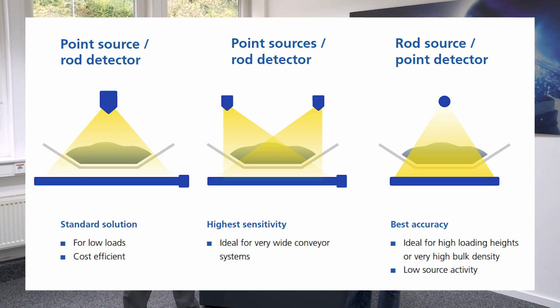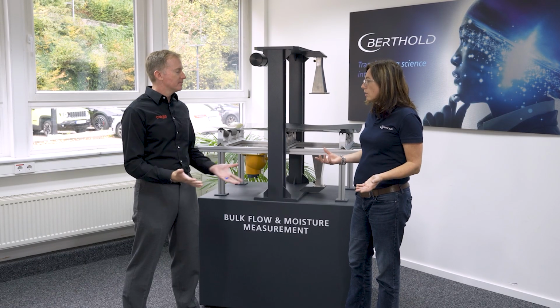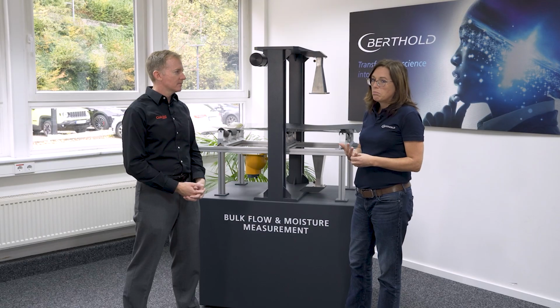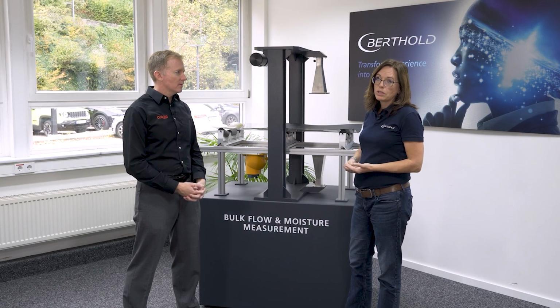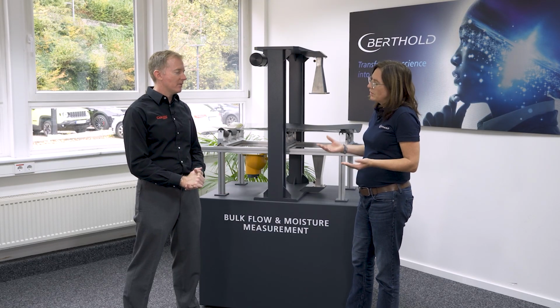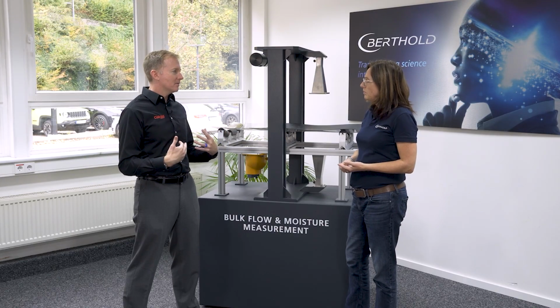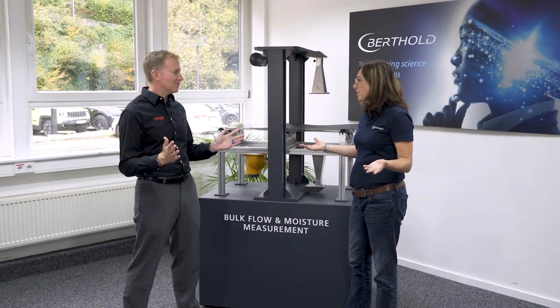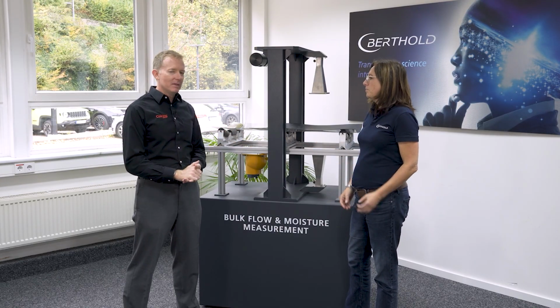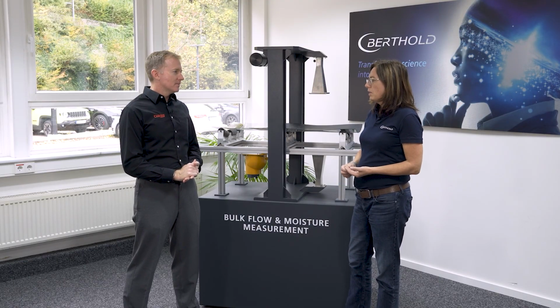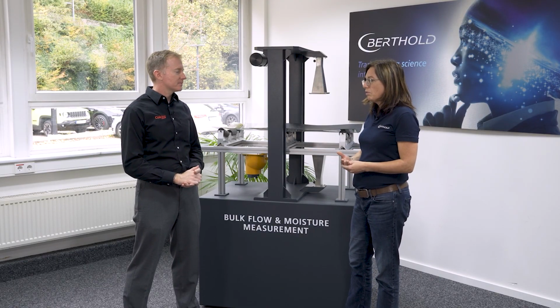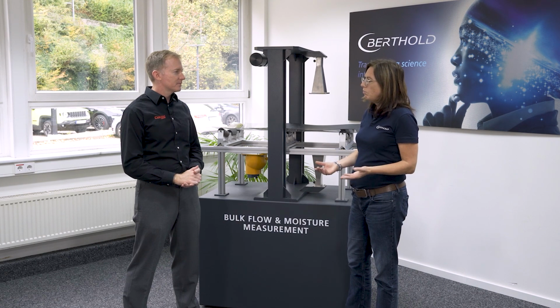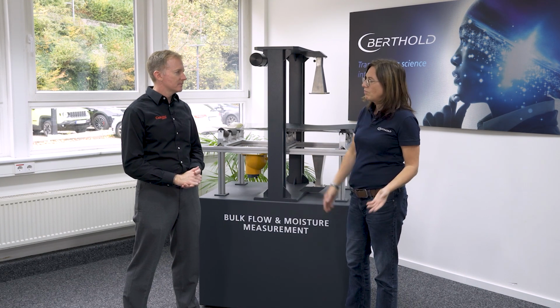It can be as accurate as 0.5% tonnage, depending on the calibration. You do have to do a reference weighing, but it can be as good as 0.5%. So you can really dial it in. I think everybody in my world would be happy with plus or minus 1%, but 0.5% would be exceptional. Yes, it takes quite a while to do a proper calibration, but once you've done that, it runs for years.